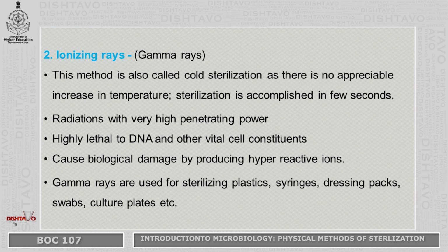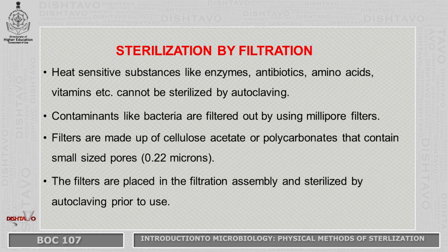Next are the ionizing rays, which are the gamma rays. This method is also called cold sterilization, as there is no appreciable increase in temperature. Sterilization is accomplished in a few seconds. Radiations with very high penetrating power, highly lethal to DNA and other vital cell constituents, cause biological damage by producing hyperreactive ions. Gamma rays are used for sterilizing plastics, syringes, dressing packs, swabs, culture plates, etc.